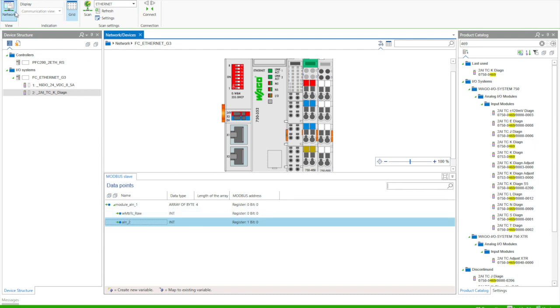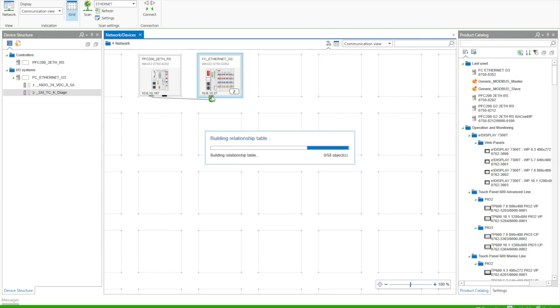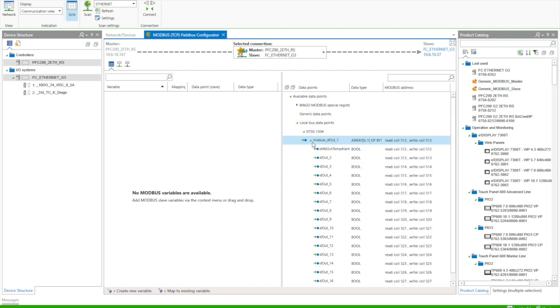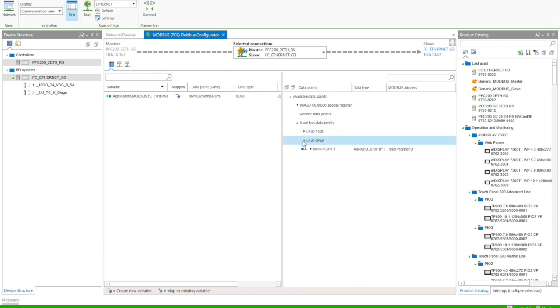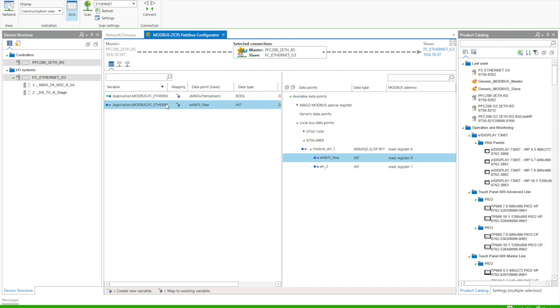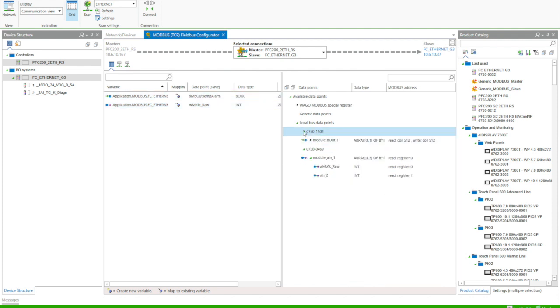Next, we're going to go back to the network view, and we need to wire these together in the network, so we simply drag the ethernet port from one to the other. Then we go to the configurator where we can actually trigger the mapping. If we go to each individual tag, right click, then you can click map. This creates the global tags in our project now.